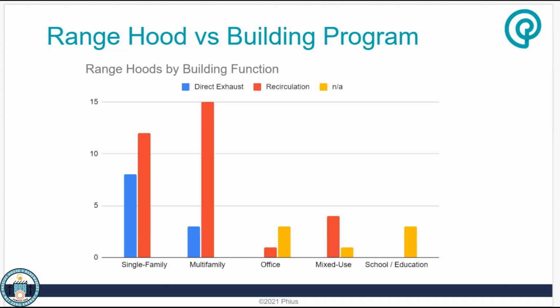You don't want to use your ERV as the only exhaust in the kitchen, because you're going to grease up the core - it's a fire safety hazard, basically, and you'll clog the core. Range hoods are exactly what's suited for pulling out grease, cooking smells, and similar. Airflows are also much higher for a range hood than for an ERV in the kitchen - you're talking a minimum of 100 CFM exhaust through a range hood, and some single family projects with big commercial grade cooktops have had 200 to 300 CFM range hoods, sometimes higher. All of those require makeup air so they don't depressurize the building. But yeah, definitely a good question.